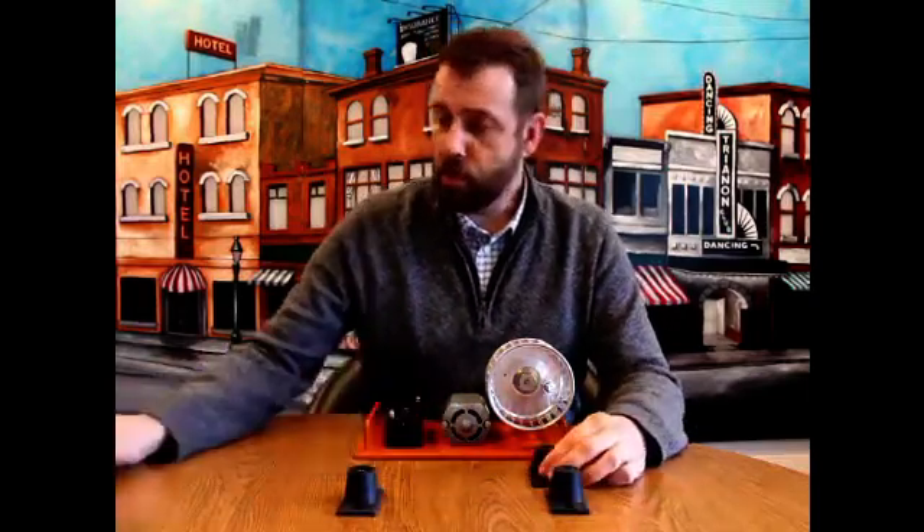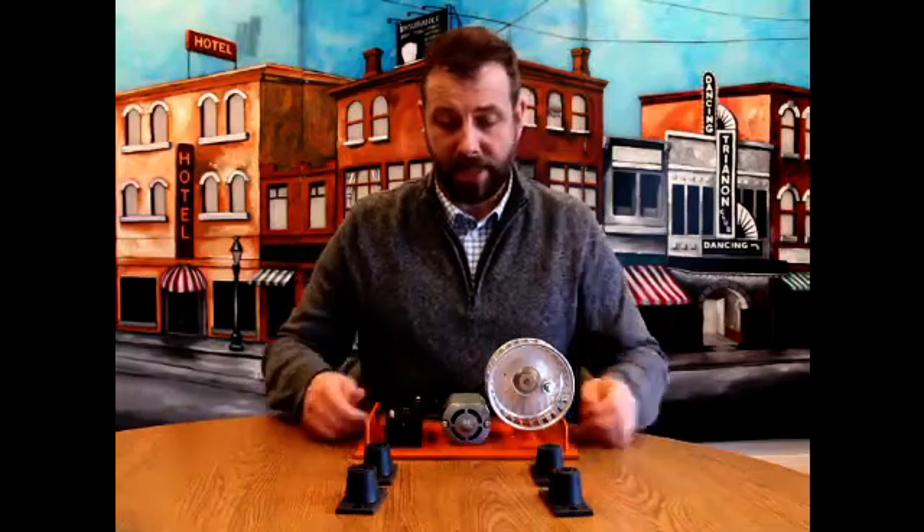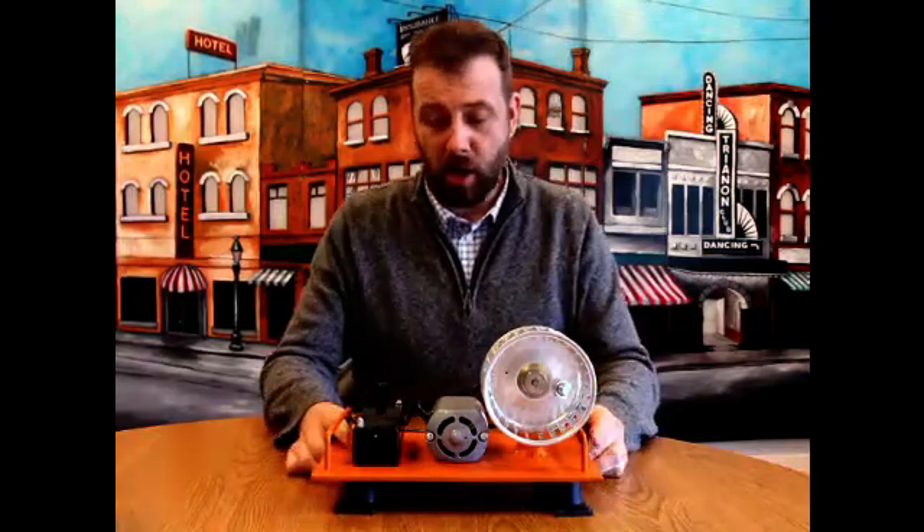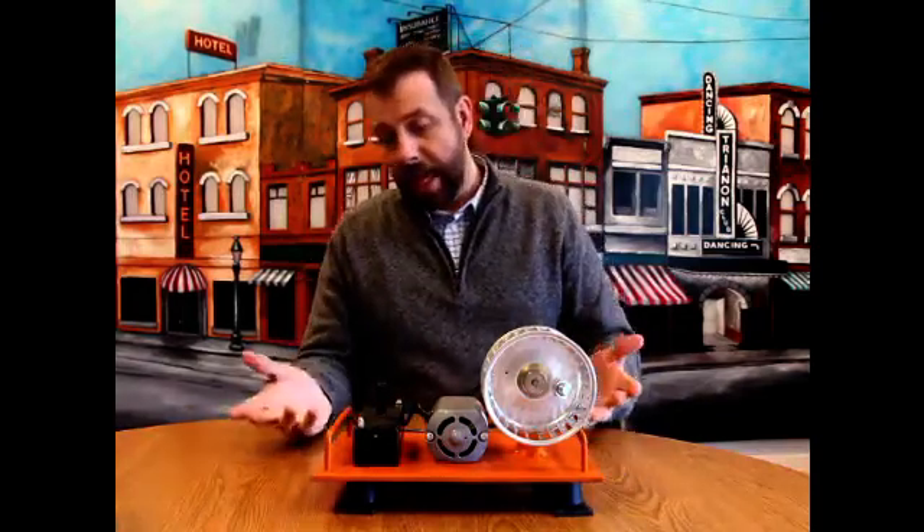It will squash down under load. So if we move these out here we should have some increase in performance and better isolation efficiency. When I put this down you can see it still doesn't deflect much — quite honestly they're under-loaded so you're not going to get much deflection. Not very noticeable anyway. Still more than the pads, but it's just not a lot.